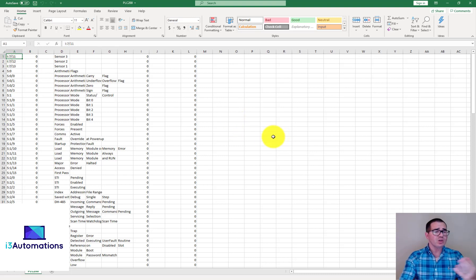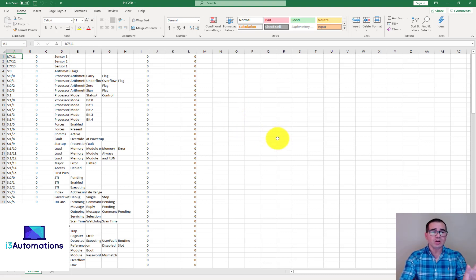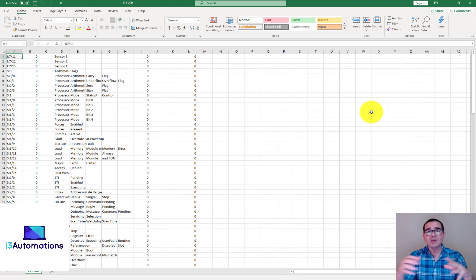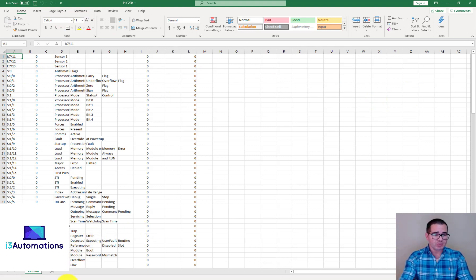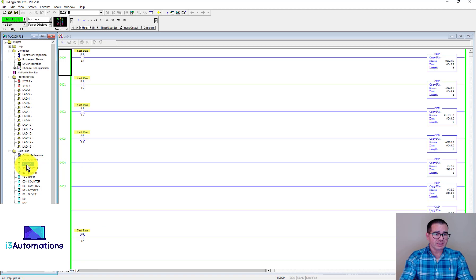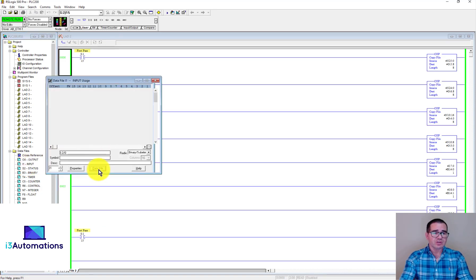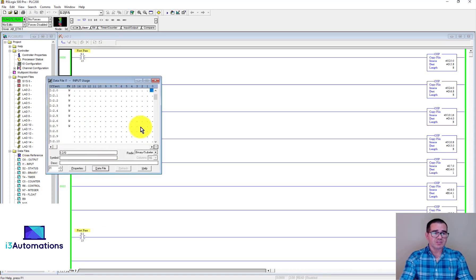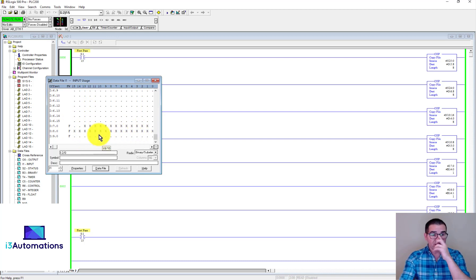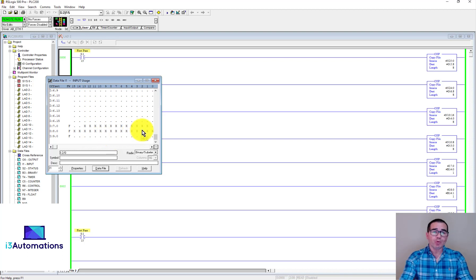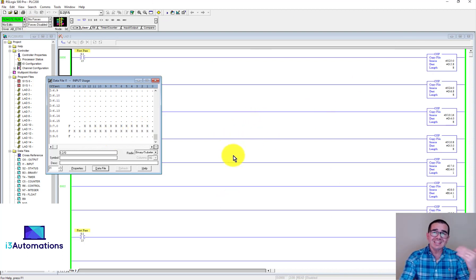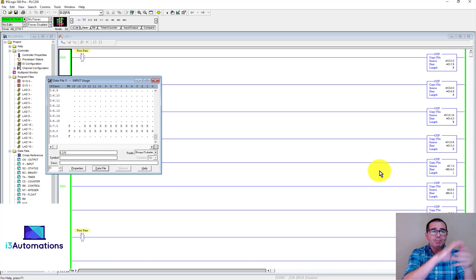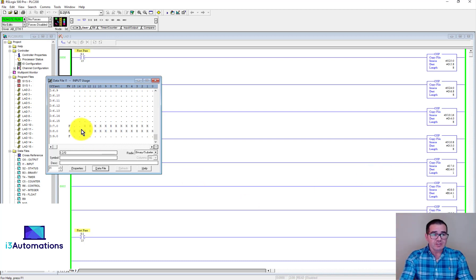You need to make sure that the PLC program has all the comments and descriptions for the tags. Let's see the PLC side. You can see just three inputs we have over there. These three inputs here have comments, and the rest we don't have comments. If you need to see all I/Os that are used, you need to add the comments in the PLC.